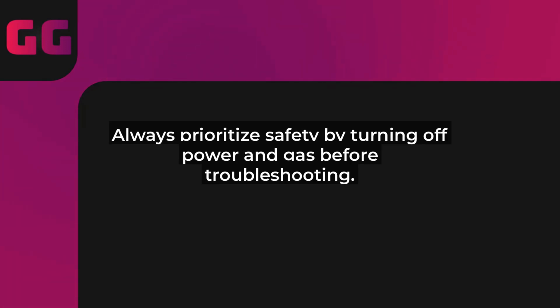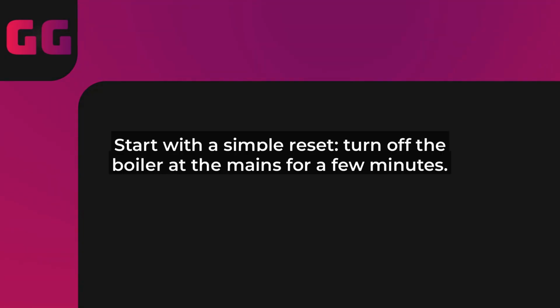Common causes include a faulty ignition electrode, problems with the gas supply, or even a blocked condensate trap. It could also stem from electrical issues or sensor malfunctions. Before you start, always prioritize safety. Turn off the power and gas supply to avoid any risks. Now, let's get to the fixes.